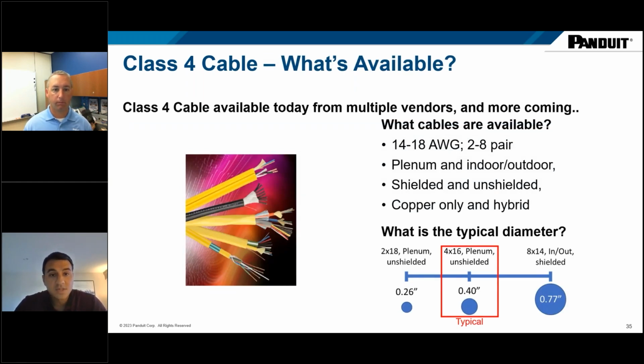So there are some Class 4 cables out there today, and we know that there are more coming into the market as well. But just so you can get an idea of what is available to you today, you'll see anywhere from 14 to 18 gauge, 2 to 8 pair. There are plenum and indoor-outdoor options. There is shielded and unshielded, copper and hybrid. And this chart here gives you an idea of how big these cables are. Here, an 8 pair, 14 gauge shielded. This indoor-outdoor one is about as big as it gets. And then this is the smaller side. Typically you'll see 3 to 4 pair, 16 or 18 gauge plenum rated cable being used inside buildings, and it's normally less than half an inch, about 0.4, 0.3.